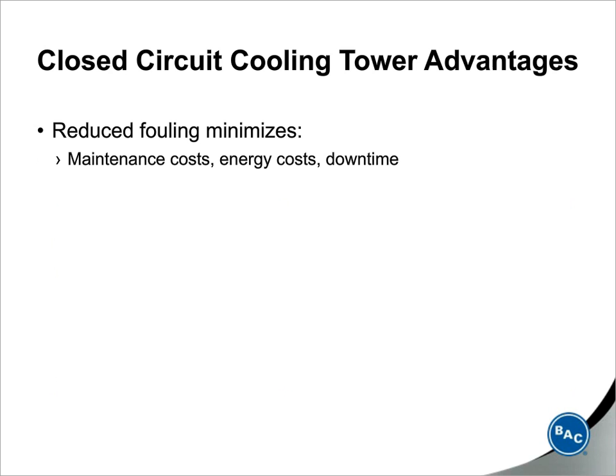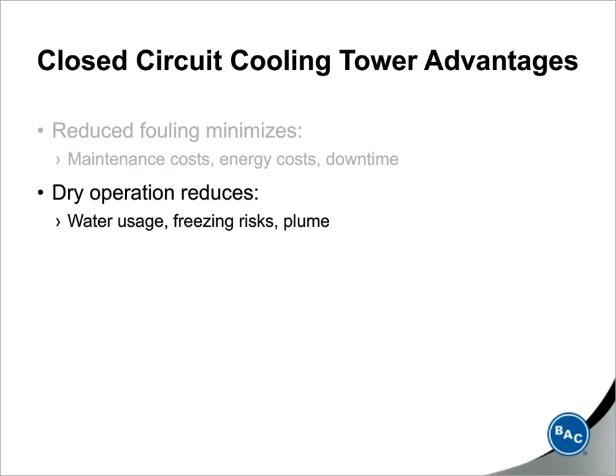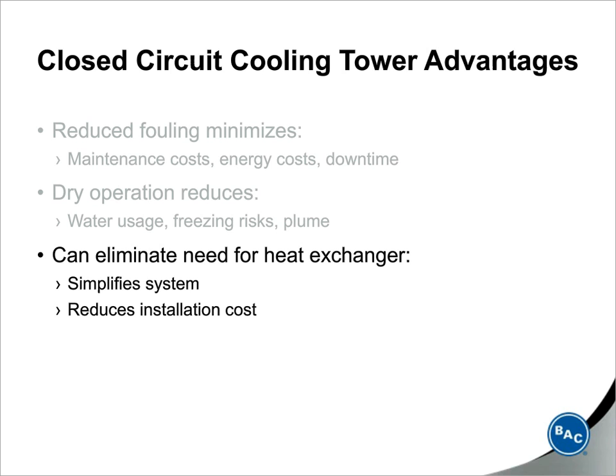So closing the condenser loop can eliminate oxygen corrosion and airborne dirt from the rest of the system, like I just discussed. And it can also eliminate the need for a secondary loop when a heat exchanger is used. Also, when you're operating a unit in harsh climates with harsh winters, you can prevent freezing and ice buildup, and you can even eliminate plume. By operating dry, you can also reduce water usage. Also, when you eliminate the heat exchanger, you can really simplify installation, and you can reduce your overall installation costs.